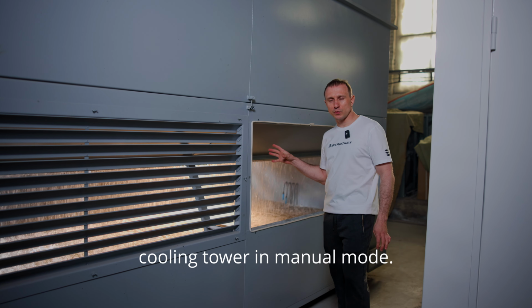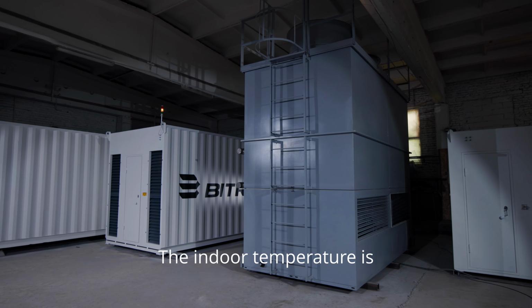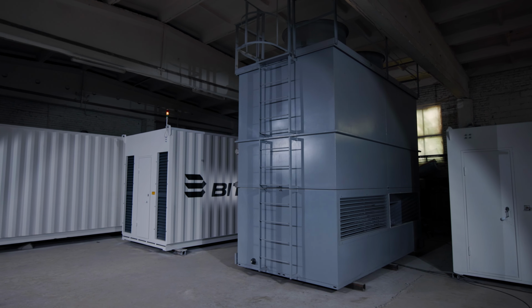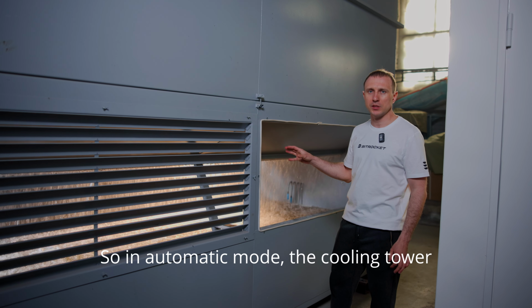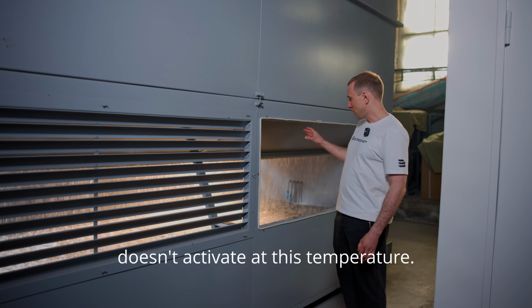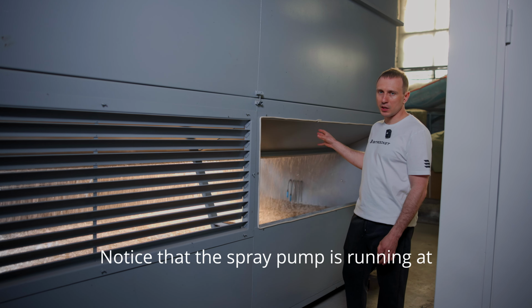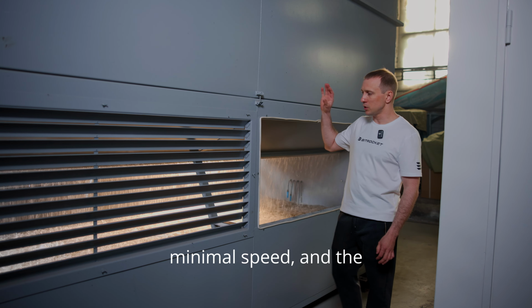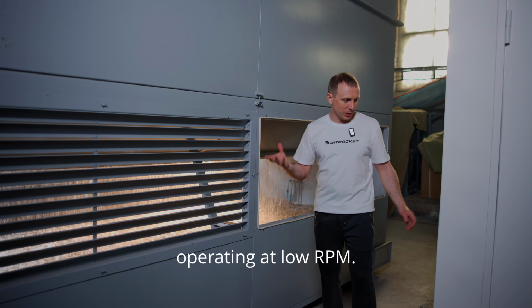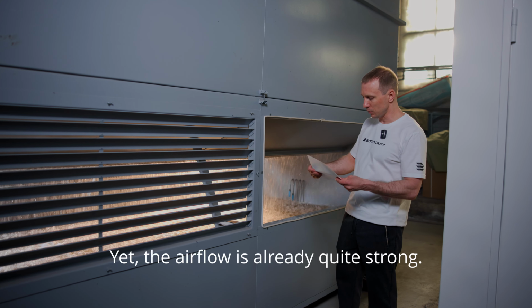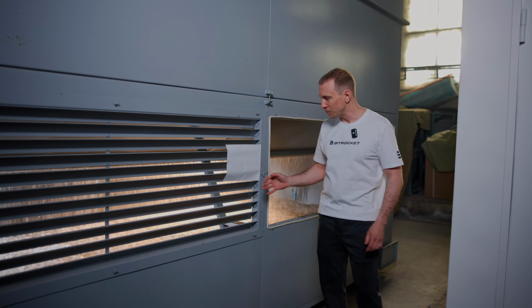We've started the cooling tower in manual mode. The indoor temperature is around 16 degrees Celsius. So in automatic mode, the cooling tower doesn't activate at this temperature. Notice that the spray pump is running at minimal speed, and the exhaust fans are also operating at low RPM. Yet the airflow is already quite strong.